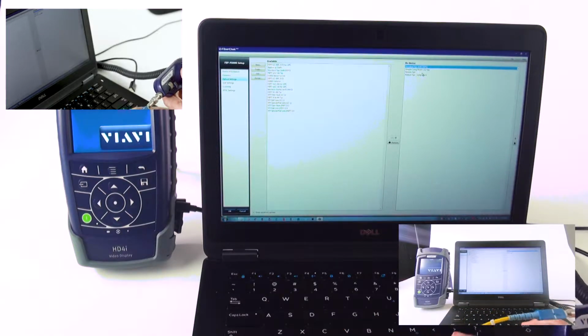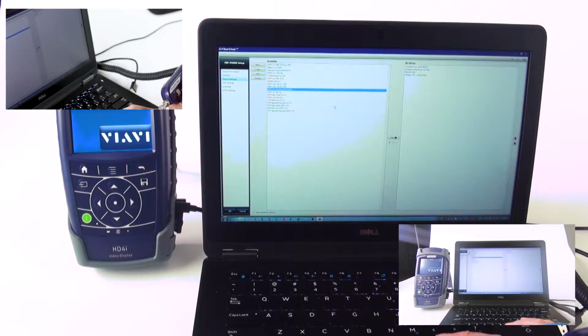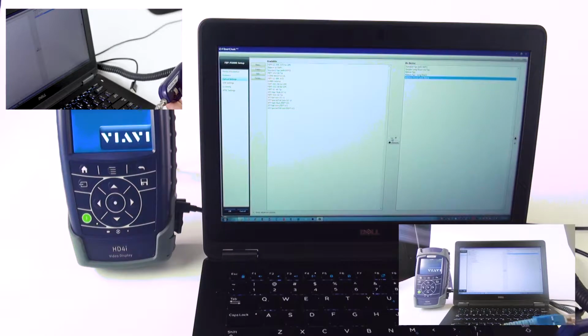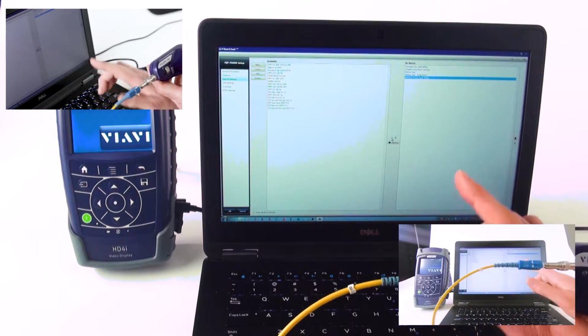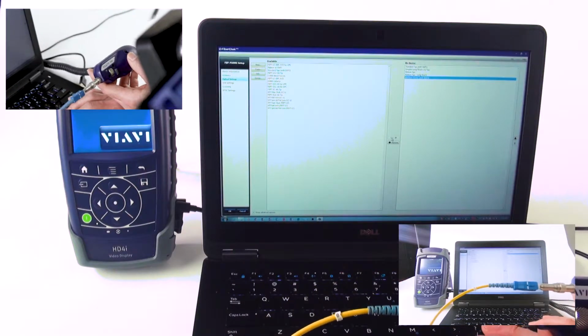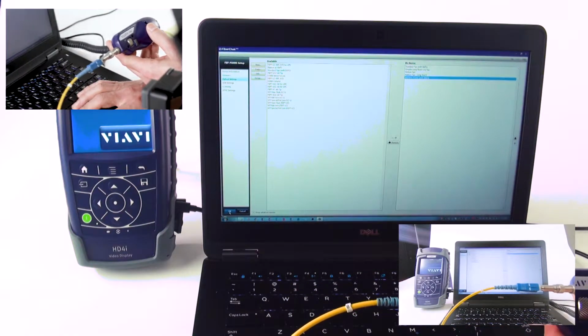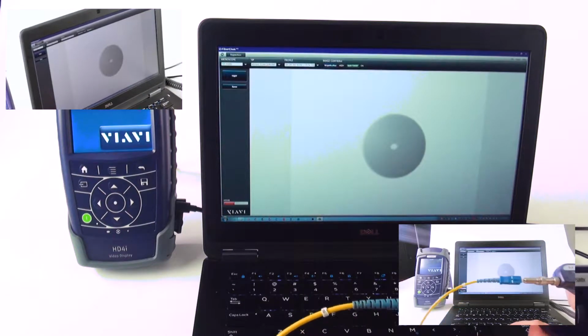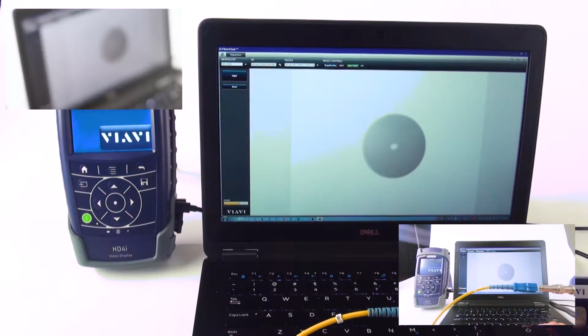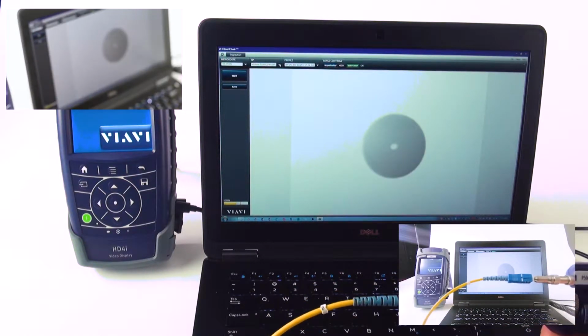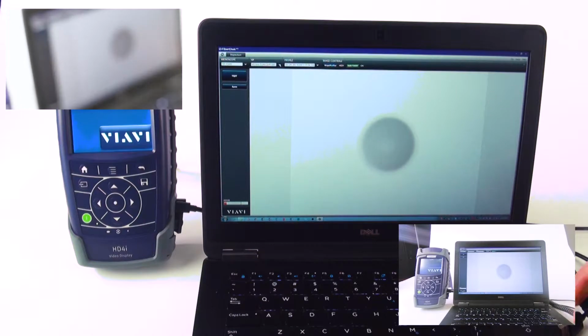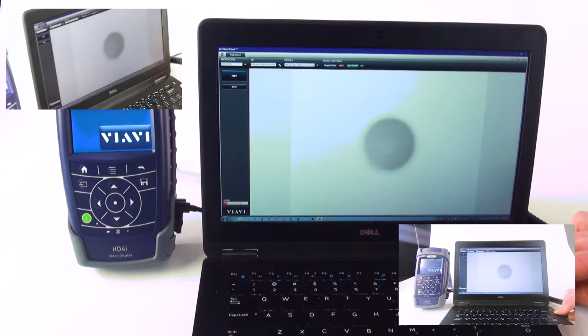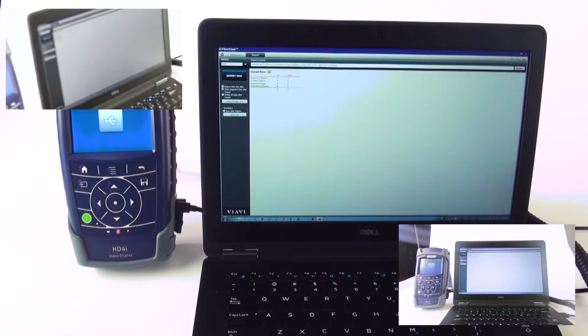Right now I'm using this standard tip, but in some applications like military and aerospace applications, there are different lenses that are used, such as here is an example of an ARINC guide with a BAP lens. That requires a different optical setting. So when I go into FiberCheck Pro, on the available side here on the left is a series of several other optical settings. If I choose Mil Aero guides with the BAP3 lens and select Add, that now added that optical setting to my device. I choose OK, and now my device is ready to go. It defaulted to that guide, that tip setting right here, so that's ready to go.